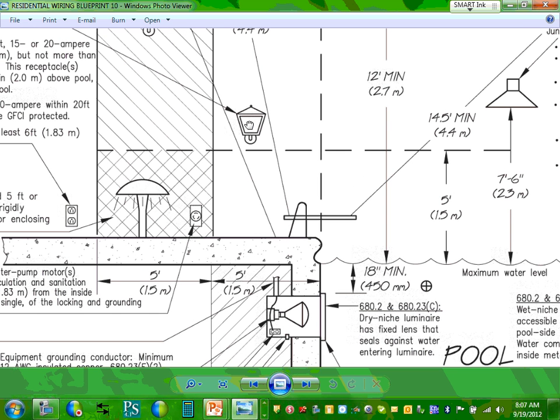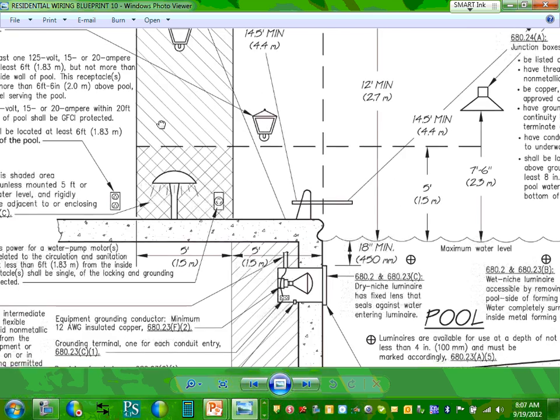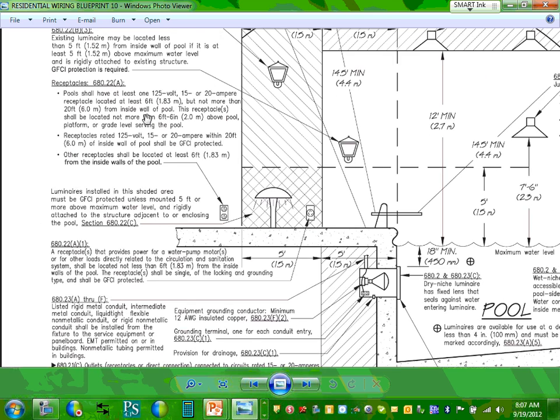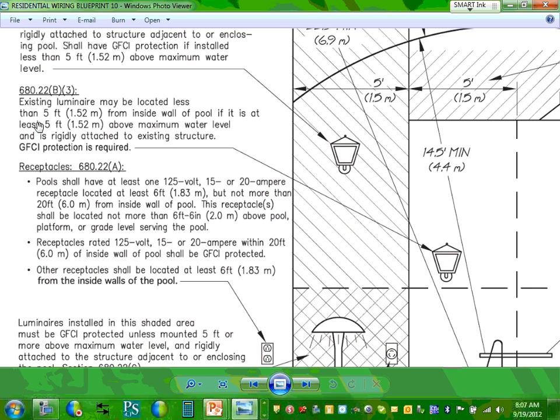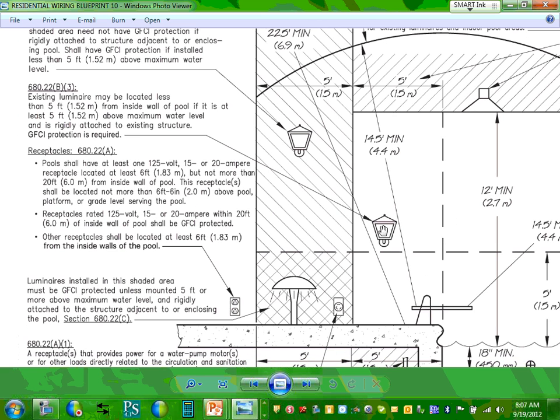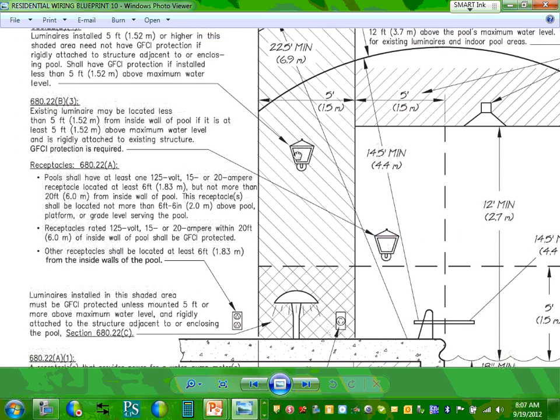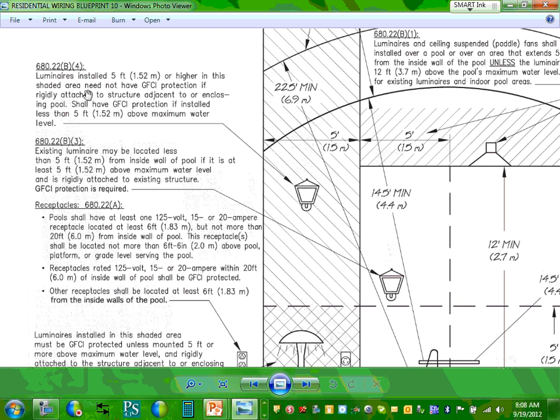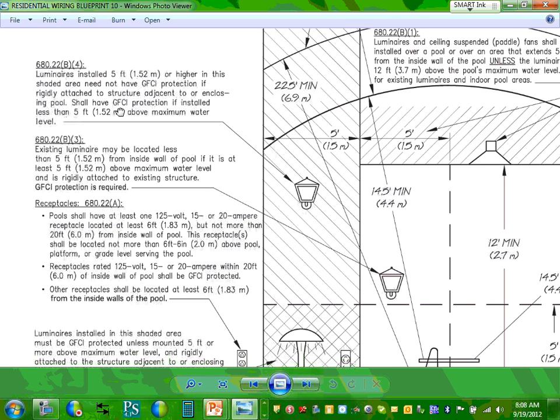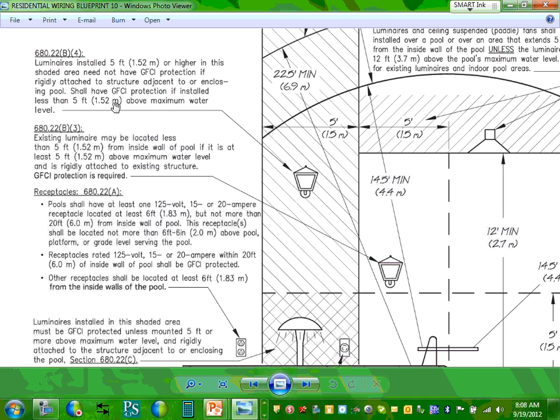If you put it within 5 feet, what requirement do you need to do for luminaires? There's a lot of information here, guys. Number one, here's the requirement for this one. For existing luminaires, they may be located within 5 feet from the inside of the pool only if they are at least 5 feet above the maximum water level. This is for existing. Normally, you have to move them away 5 feet, put them in this area, and they have to be 5 feet away from the swimming pool, and they have to be GFCI unless they are low voltage contact limit. Can you guys see that one? So 5 feet away from a swimming pool is kind of a sacred cow. You don't put anything closer than 5 feet away from a swimming pool. So that's for the light.